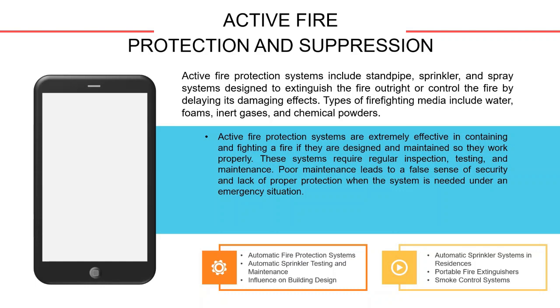Active fire protection and suppression. Active fire protection systems include standpipe, sprinkler, and spray systems designed to extinguish the fire outright or control the fire by delaying its damaging effects. Types of firefighting media include water, foams, inert gases, and chemical powders. Active fire protection systems are extremely effective in containing and fighting a fire if they are designed and maintained to work properly. These systems require regular inspection, testing, and maintenance. Poor maintenance leads to a false sense of security and lack of proper protection when the system is needed under an emergency situation.